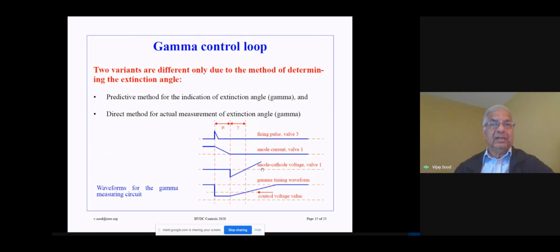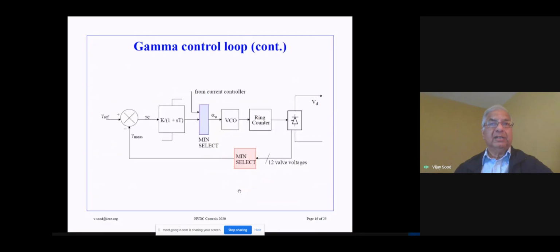This is the anode to cathode voltage, the valve voltage for valve 1. So once the current has gone down, now the reverse voltage is seen. So we detect this point, and at this point we initiate a timing signal, and this will now give us an indication for the gamma value that we want to set. So here is the measurement for gamma, the reverse voltage which appears across valve 1. This is the gamma measurement, so we can utilize this gamma measurement in the controllers over here. So this is one of the variations.